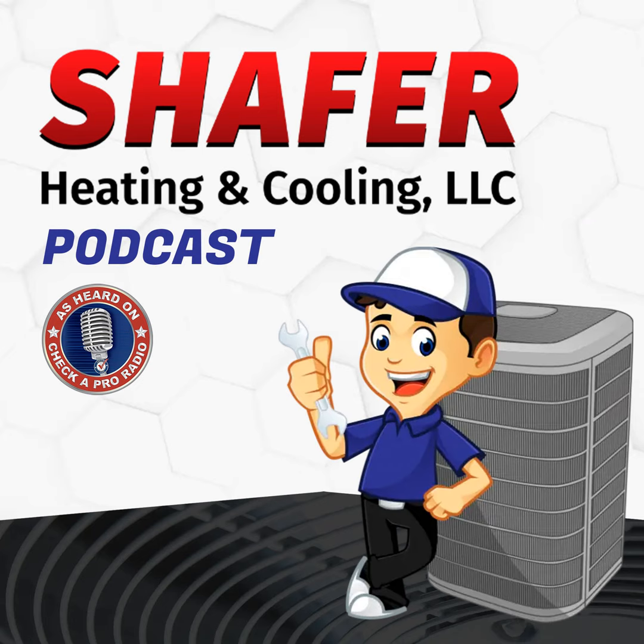which are great. So also, what people can do, which I don't necessarily recommend, depending on how much thrust you've got going through your ductwork, is sometimes double filter. They'll put a very inexpensive filter in their return just to catch some bigger stuff, so the media filter has to do less work. That can be done, but like you said, it's usually not recommended, because most duct systems would have to be oversized to allow for the extra restriction, what we call pressure drop.